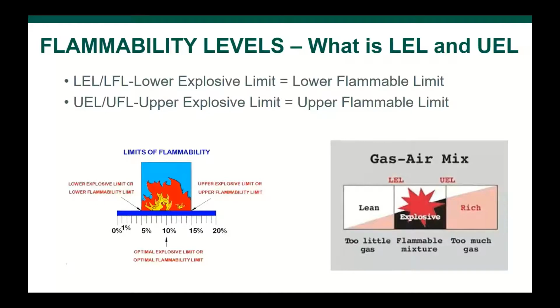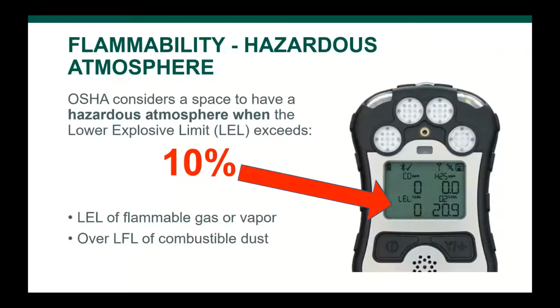So that's why there is that mixture of air and gas that is going to be optimum for fire or explosion. And that's why the limit is 10%. If there's too little gas, it's going to be too lean, it's not going to burn, or it's going to be too rich and then it's not going to burn, it's not going to blow. So that's why OSHA considers a space to have a hazardous atmosphere when the lower explosive limit, the LEL, exceeds 10%.